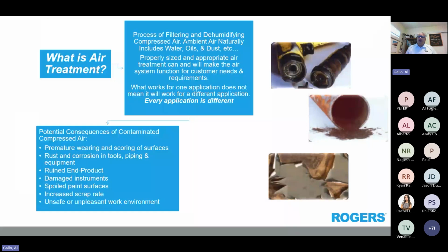To start off, let's talk about what air treatment is. Air treatment is basically the process of dehumidifying compressed air and filtering it so that the customer can use it at their point of use, whatever they're making, the widget, or however they're using air to convey. If you don't put in the appropriate air treatment for your application, you could have a lot of different problems, spoilage and wear and tear of equipment. We get a lot of calls: hey, my impact wrench only lasts 6 months between rebuilds. How can I make it last longer?